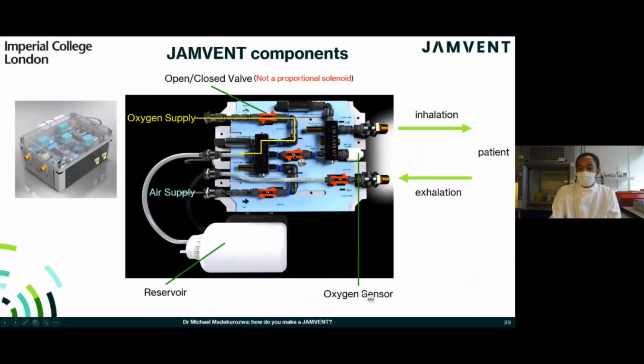The system has an oxygen sensor, which measures the oxygen of inhaled air. It also has a pressure transducer, which measures the pressure inside the reservoir. This is important because when we're delivering a breath, we want to deliver a set tidal volume. The way that we measure volume is by measuring changes in pressure through Boyle's law, as was discussed earlier by Dr. Joseph Sherwood. So we have a pressure transducer here as well, which measures the pressure in the lung of the patient. This is important for two reasons.